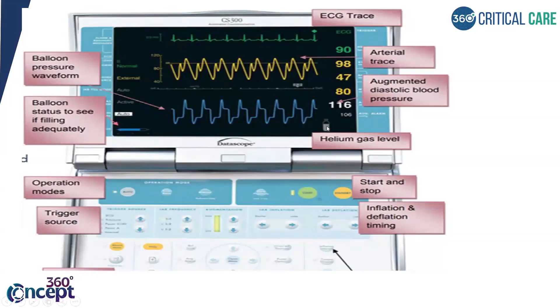The standby switch is mainly used just before we remove the IABP, or sometimes during the weaning of your patient from IABP. This is the common trace waveforms, and you can see a small cylinder shown here. This shows the level of the helium gas. You need not have a full cylinder, and even if the cylinder is near empty, don't worry about it, because we are not giving helium to the patient. It's not like an oxygen cylinder where it can get exhausted. Whatever goes in comes back again, so no need to worry about it. This is the helium cylinder which is seen.